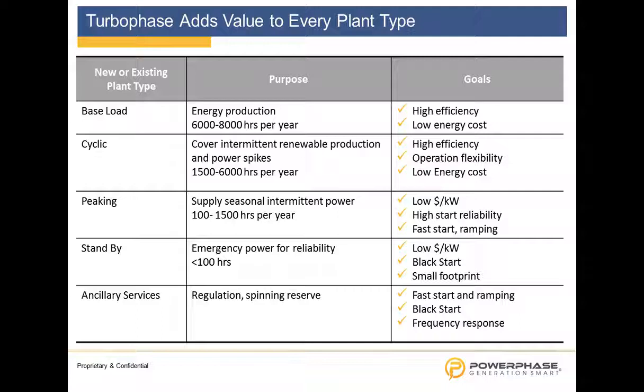And then ultimately standby, Turbophase, as I mentioned, the engines are typically used as gensets. We have the ability to put a black start 2.5 megawatt generator on our unit, whereby the Turbophase module can be used not only to make air, but we can clutch out the compressor, and we can clutch in the generator to make 2.5 megawatts of black start power per box. And this allows us to be used for emergency standby or black start of the facility.